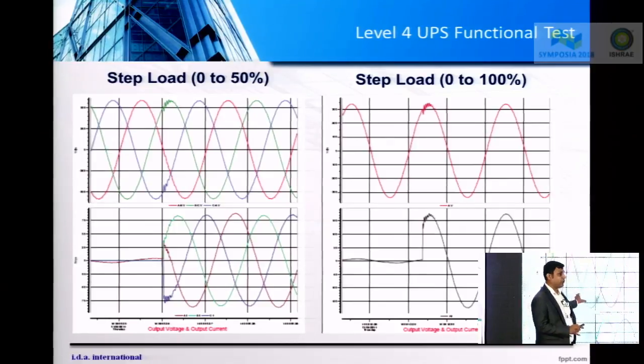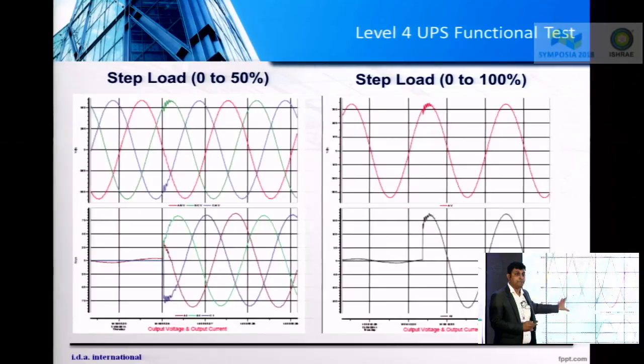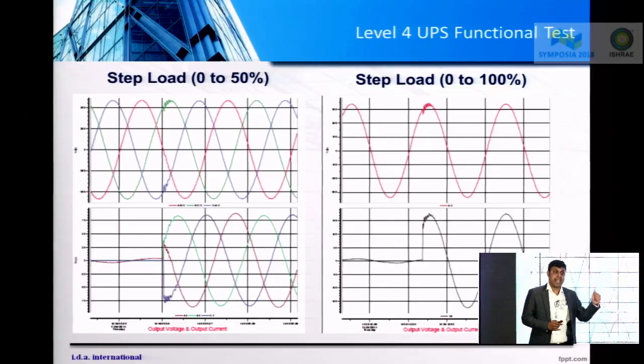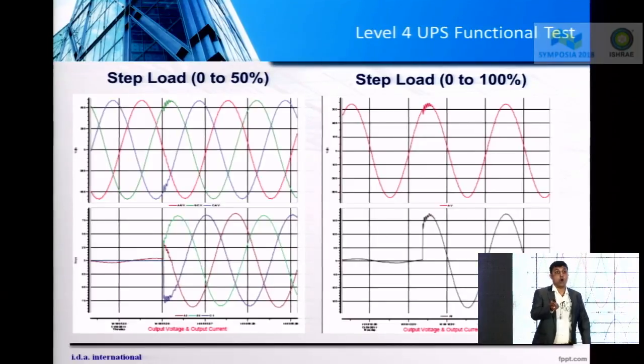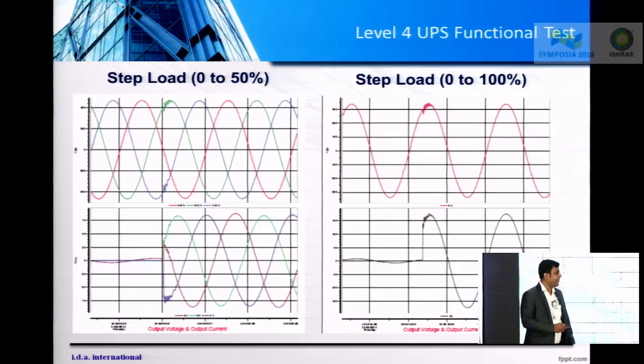When you do this step load test, it is important to identify that there is no major distortion or break, because that would be disastrous for a data center. So it is very, very important to verify the step load test at 0 to 50% condition, 0 to 100% condition, or 50 to 100% condition.